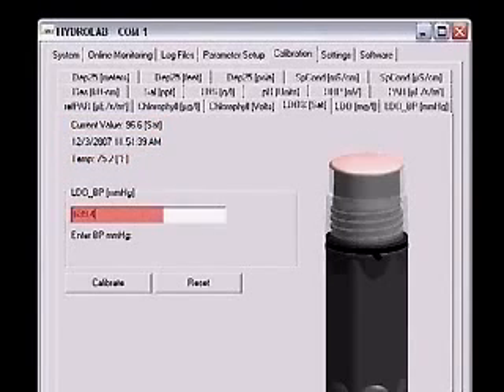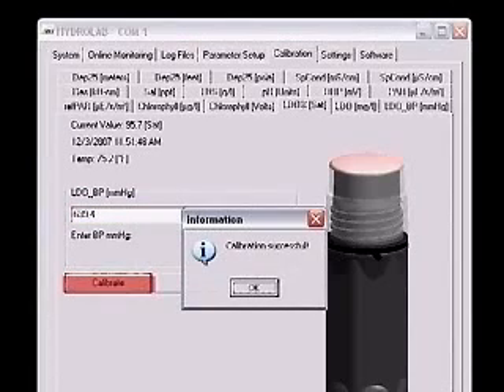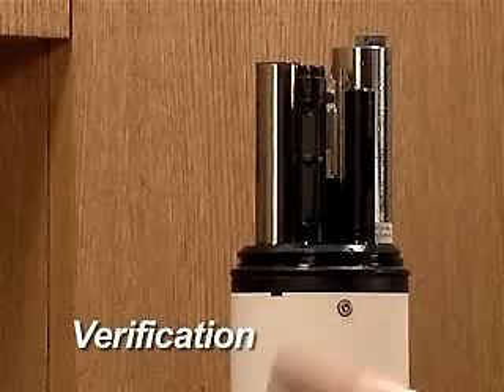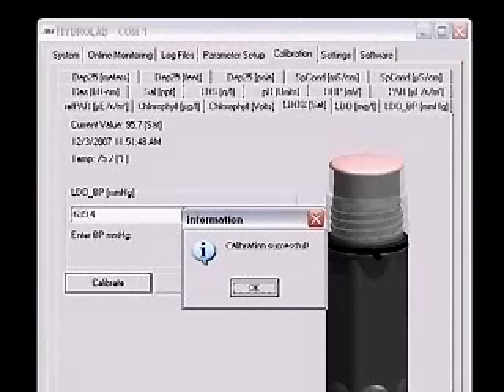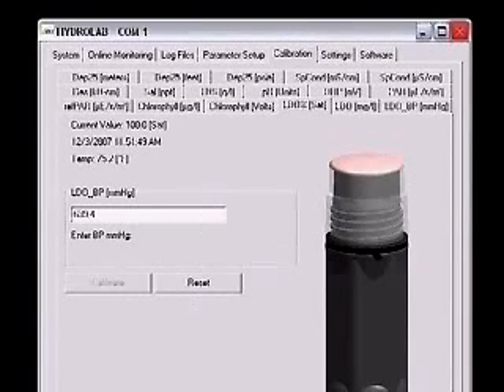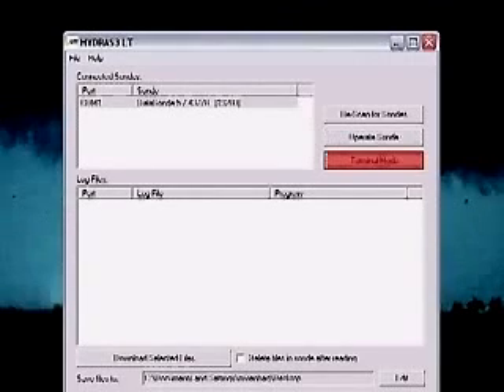Enter the current absolute barometric pressure in millimeters of mercury in the box. Click Calibrate. A calibration successful message will be displayed. Verification. Click the red X in the upper right corner and close the calibration window. In the connection window, click the button labeled Terminal Mode.